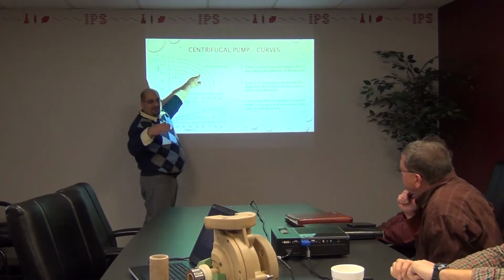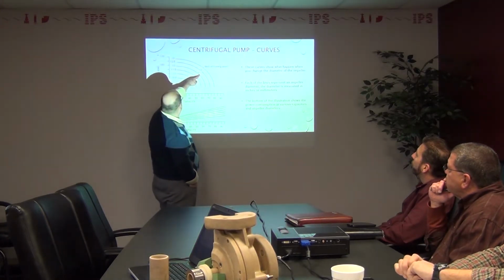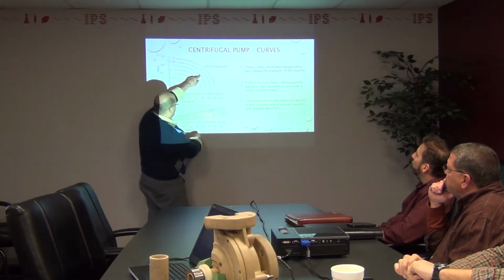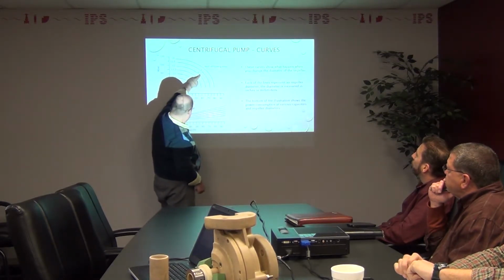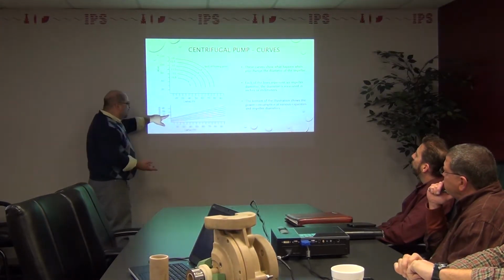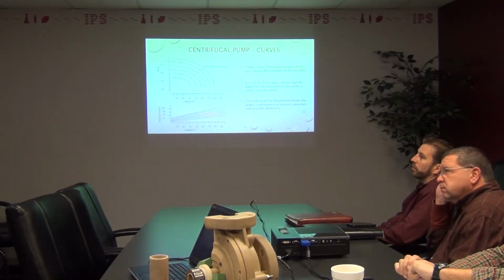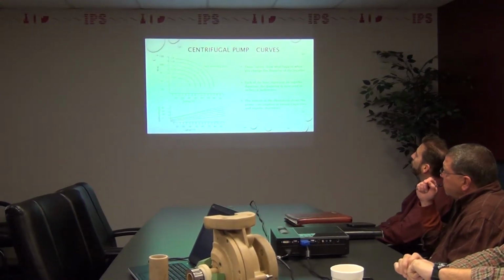The best efficiency point is our goal, that's where we want to hit. Rarely do we ever get there. We want to get as close as we can, but don't be concerned if you don't get there. Plotting this, I'm at an 11.5 inch trim. So I come down to my 60, and then I plot this back here, and I'm roughly around a 20, probably a 25 horsepower motor. So 11.5 impeller trim and a 25 horsepower motor to do that application.